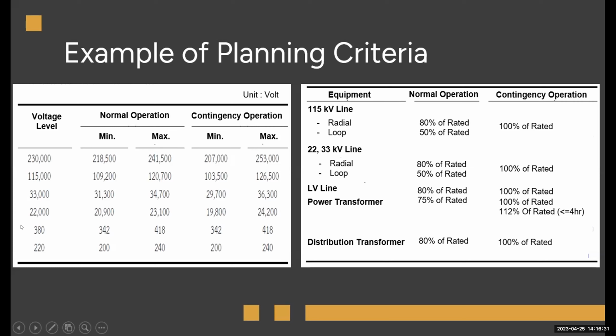And the second is because the distribution transformers don't have an automatic load tap changer, so we can't change the tap at the distribution transformer, so the voltage level is the same in the two conditions. For the equipment, it is similar to the voltage level. For the 115 kV line, we limit the line current load to not more than 80% for the radial system, and for the loop line it is 50%.